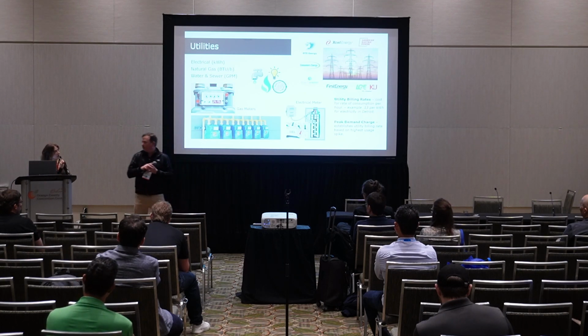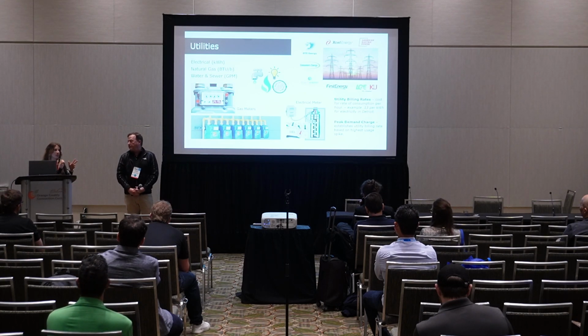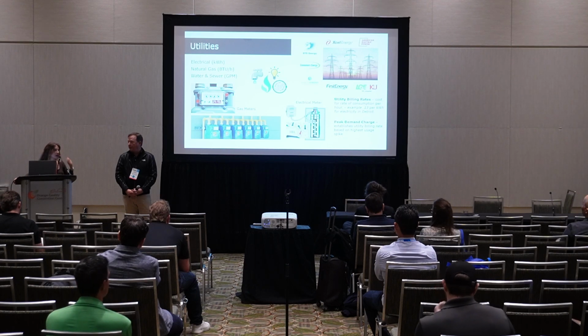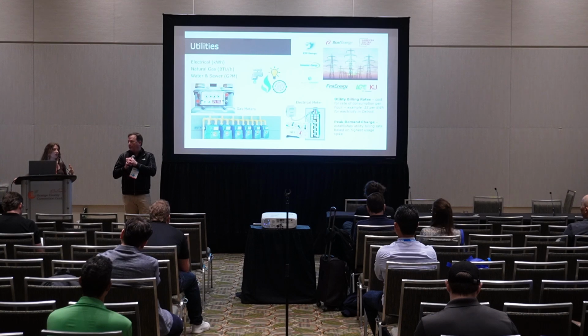I'll just add a little bit about the peak demand charge too. We have clients that like to deal with it in different ways. If I'm doing an energy study, I'm going to break down the demand and the kilowatt hours separately, and combine those two costs. There are times where we installed a big heat pump, and our kilowatt hours went way down, saving a lot there, but our demand charges went way up. So you don't want to forget about that. We want to look at both, because your peak demand charge can be pretty significant if you're running a bunch more electrical equipment. Something to keep in mind.